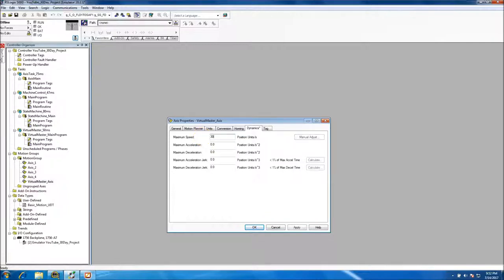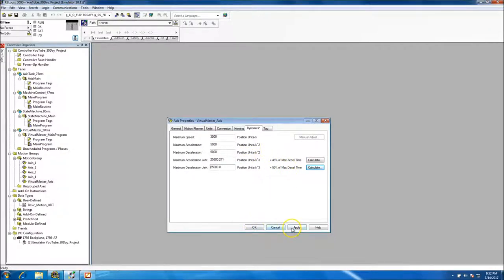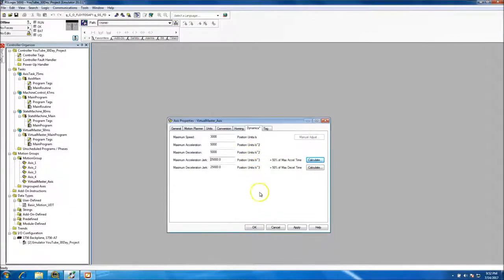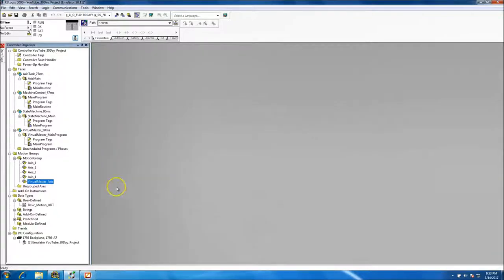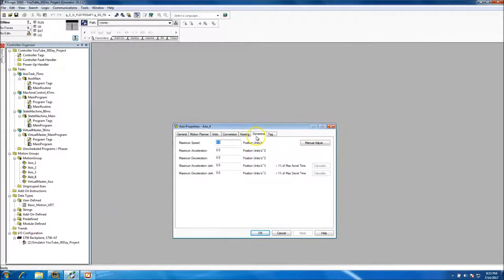Homing is set to absolute zero. For dynamics, we need to put in speeds and other values. We'll call the speed 3000 and set the acceleration — roughly at 50% — and then our system will be set up. We may come back and change these values later.